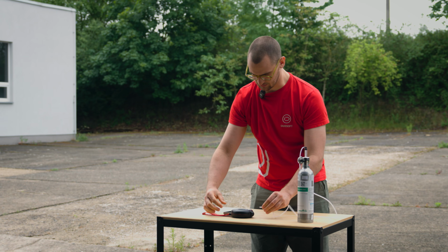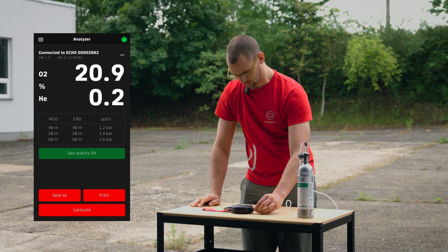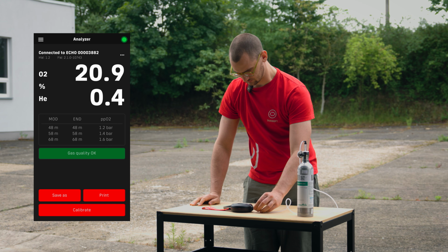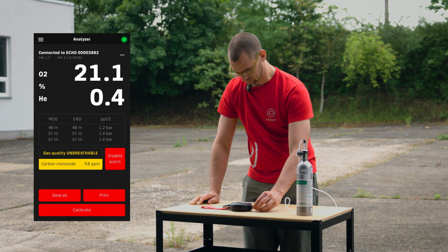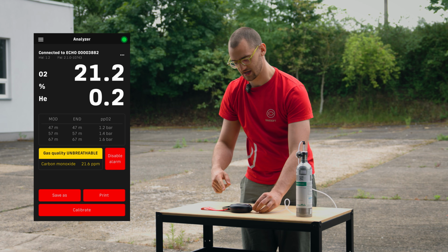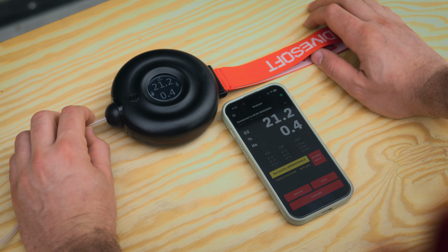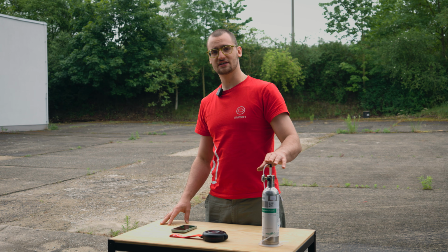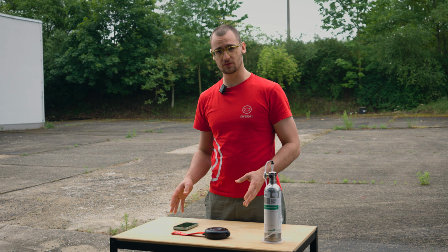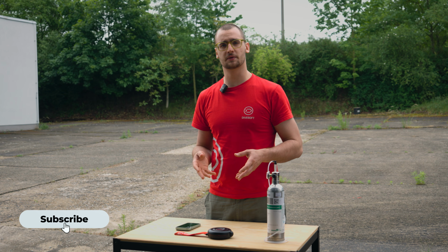I'm going to connect it up to the Echo. And here you can see the Echo detects bad gas and immediately alerts the user. Now we have finished the test. The Echo will alert the user if the concentration of carbon monoxide is above 5 parts per million. If you want to know a little bit more about the Echo, you can go and check the website down below.